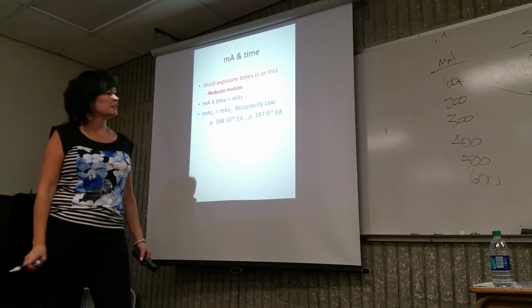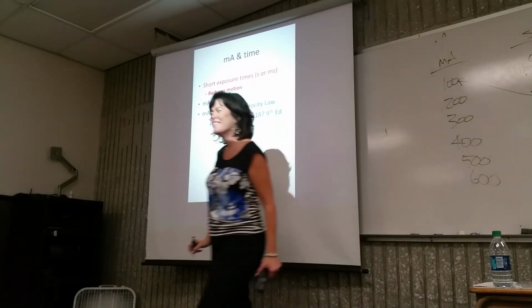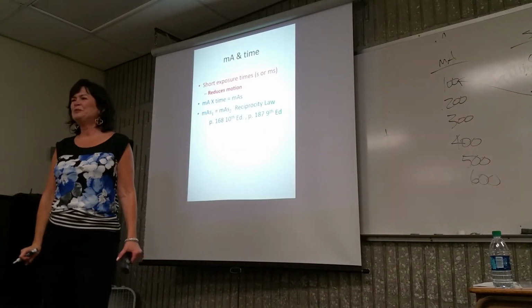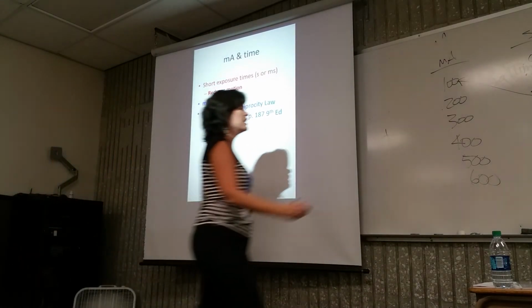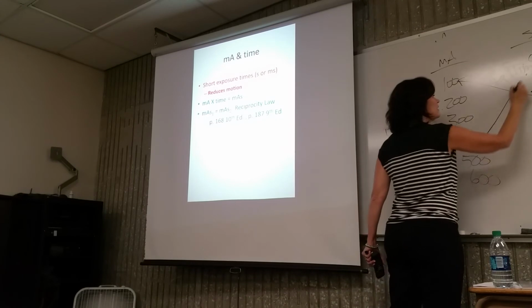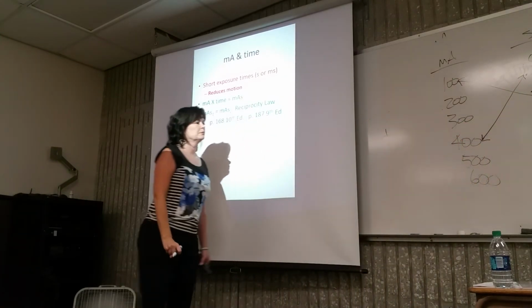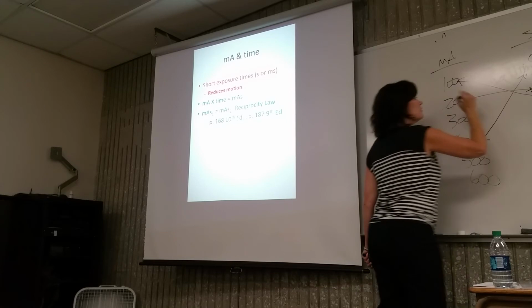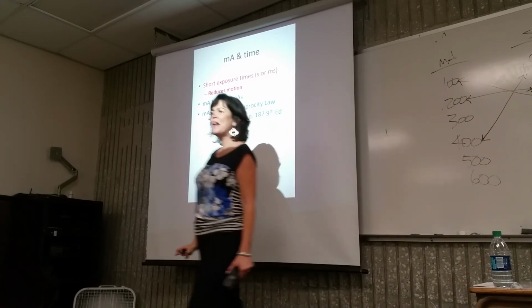What else? 400 at 0.025. 200 at 0.05. Will any of those give you 10 mAs?